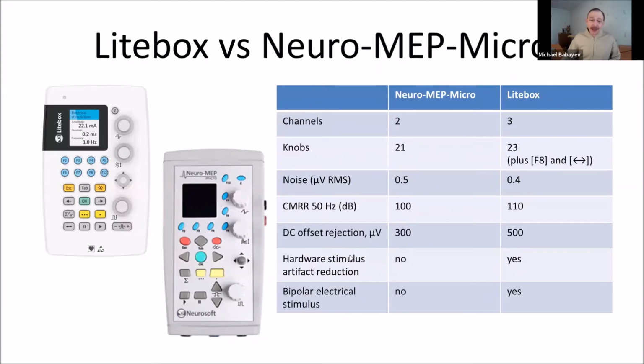Also in Litebox, we put some special features. One of them is hardware stimulus artifact reduction. It is a special electronic scheme that suppresses stimulus artifact. And we made it for the first time in our history. It is the first device. Also in Litebox, we have bipolar electrical stimulus, when the first part of the stimulus can be, for example, plus, and the other will be minus. It is also useful for suppression of the stimulus artifact.